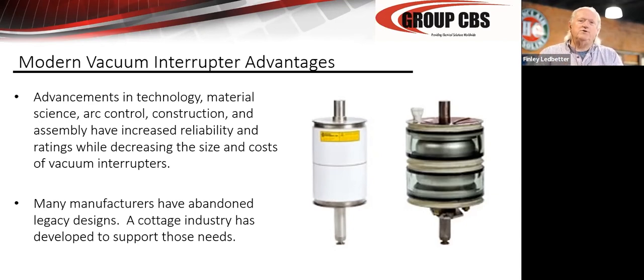The modern interrupters are built inside a vacuum furnace. They're assembled and brazed in one shot method, so there's no pinch tube on them. Typically modern interrupters are pretty good, but there again, we do see quite a few fail directly out of the box, and you do see a lot of the Chinese stuff that comes in that has a very high leak rate. So there are some terrors on the edge of the world here. Absolutely, there are manufacturers, Siemens, ABB, Mitsubishi, for instance, Hyundai, that have very low leak rates, and I feel very good about. Probably shouldn't have said that.